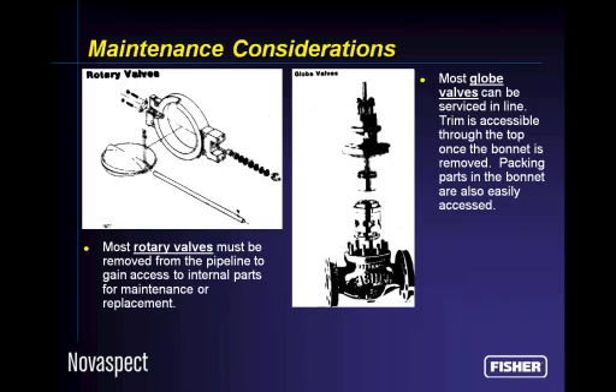Your maintenance staff might have some particular preferences regarding valve types that you might use. From a maintenance standpoint, a top-guided, top-entry globe valve, which I'm pointing to now, is very easy to maintain while the valve is in line. You merely unbolt the bonnet from the top of the valve and pull it off, and you get access to every one of the components in the valve: all the gaskets, plugs, cages, bushings, seat rings, stems. It's all available there for you to inspect and repair as required. Unfortunately, rotary valves don't have that same benefit. Anytime you need to inspect or repair or replace a part in a rotary valve, it has to be removed from the line to get access to the internal parts. So your maintenance staff may have something to say about the type of valve you use in any particular application.